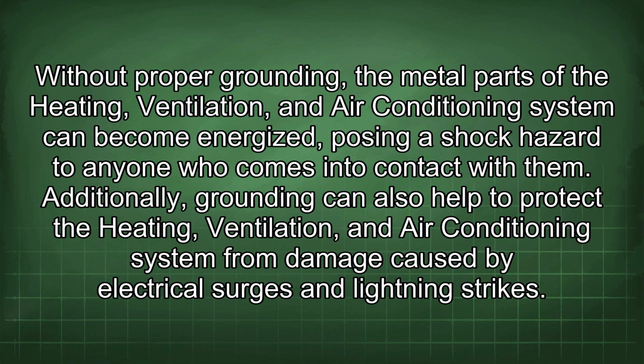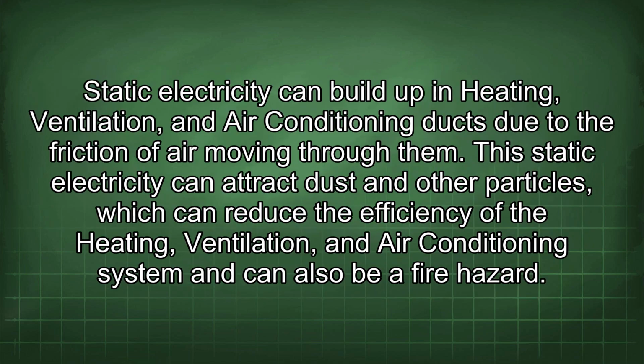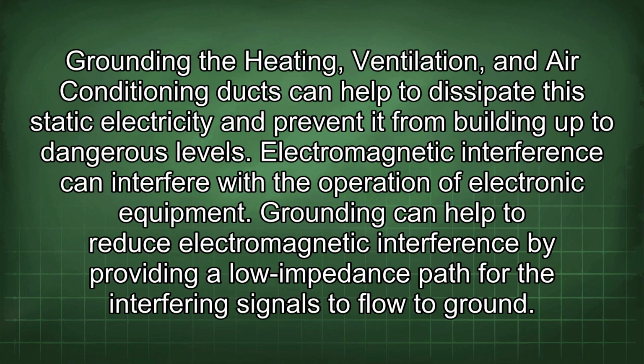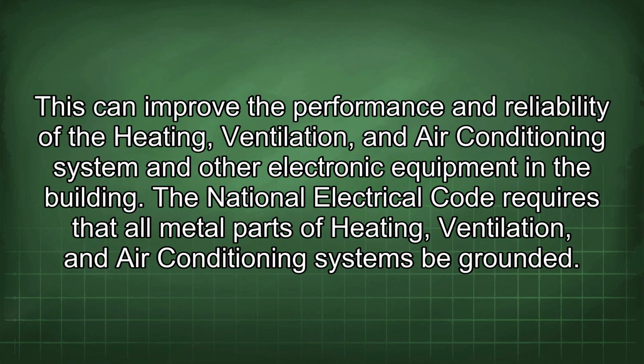and lightning strikes. Static electricity can build up in heating, ventilation, and air conditioning ducts due to the friction of air moving through them. This static electricity can attract dust and other particles, which can reduce the efficiency of the heating, ventilation, and air conditioning system and can also be a fire hazard. Grounding the heating, ventilation, and air conditioning ducts can help to dissipate the static electricity and prevent it from building up to dangerous levels. Electromagnetic interference can interfere with the operation of electronic equipment. Grounding can help to reduce electromagnetic interference by providing a low impedance path for the interfering signals to flow to ground.